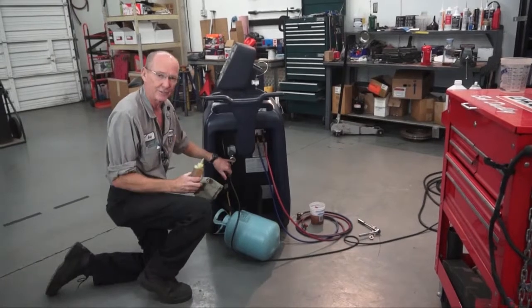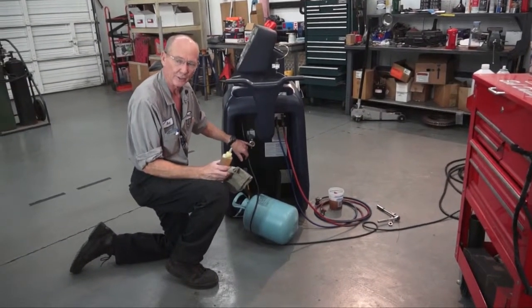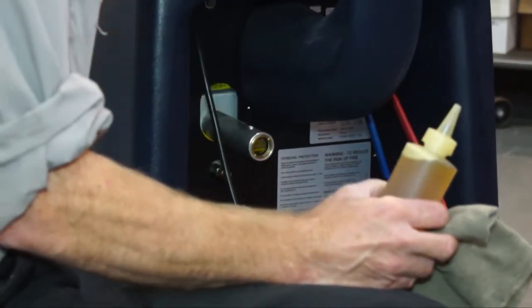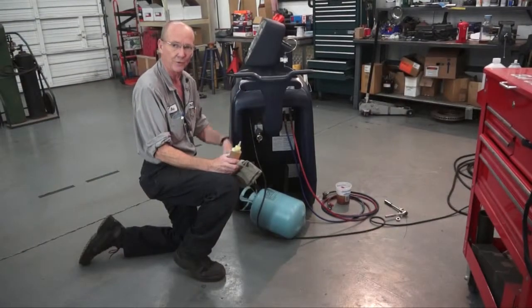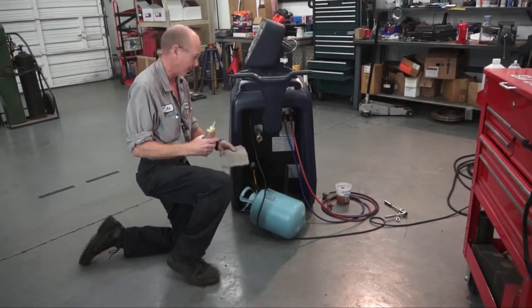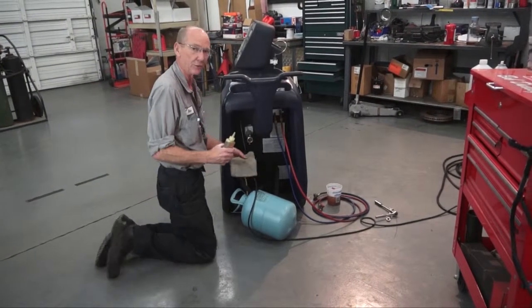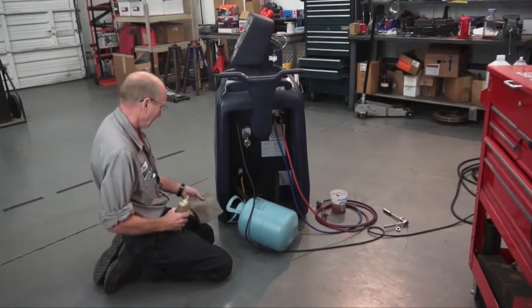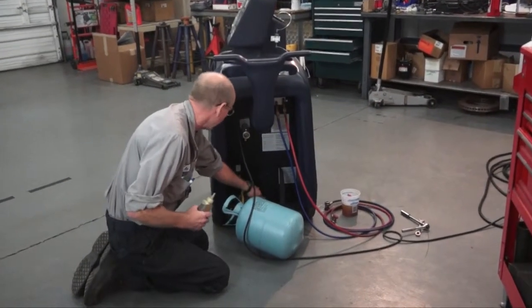So you have a sight glass here. You'll notice some residual oil laying in the bottom of the sight glass. That's okay. You're not going to get it all out. You can tip it back and forth if you want to try to get it all out, but it's not going to matter. There's just a little bit of residual oil left in the bottom. So I just put a towel down here.